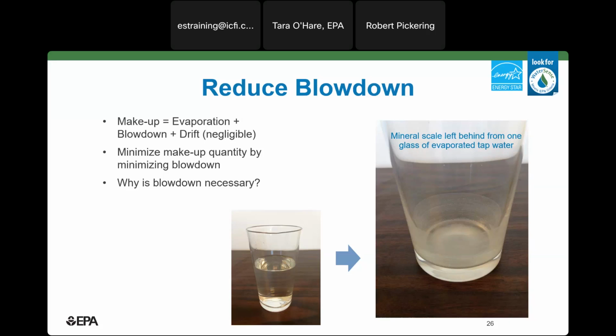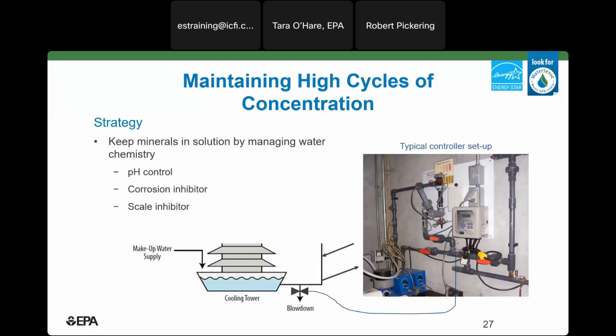There's some water that is regularly discharged. This is the blowdown to keep these dissolved solids in check. The blowdown is typically controlled by a conductivity meter or a controller. Careful blowdown control, as I said, offers really the best opportunity for savings in a cooling tower system. So this background establishes the basis for saying that by maximizing your cycles of concentration and reducing the blowdown, your system efficiency will improve.